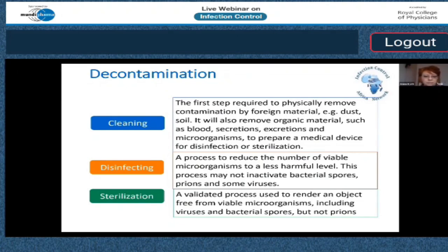And we will see later on, using the Spalding classification, how we make sure that we reduce the number of viable microorganisms to less than a harmful level on the instrument before we can start using it. And when we know the type of instrument, whether it is critical, semi-critical or non-critical, we follow the next step by validating a process, putting it through the autoclave to make sure that this object is free of any viable microorganisms, including viruses and bacterial spores, but not prions.